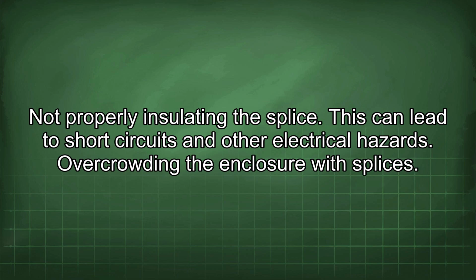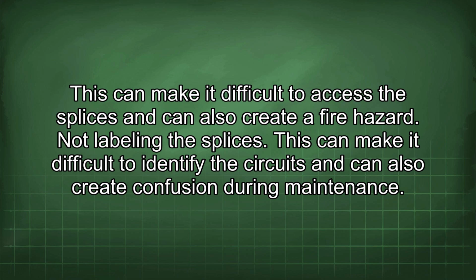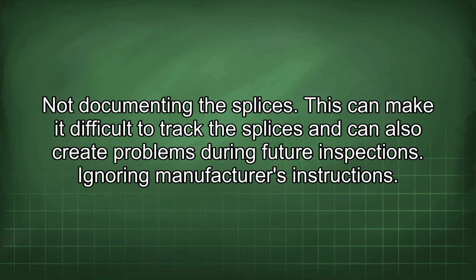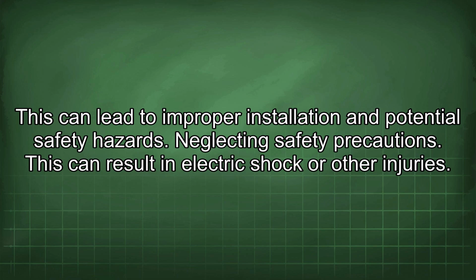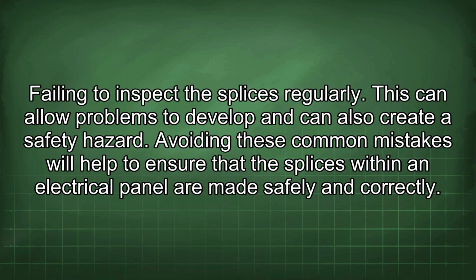Overcrowding the enclosure with splices. This can make it difficult to access the splices and can also create a fire hazard. Not labeling the splices. This can make it difficult to identify the circuits and can also create confusion during maintenance. Not documenting the splices. This can make it difficult to track the splices and can also create problems during future inspection. Ignoring manufacturer's instructions. This can lead to improper installation and potential safety hazards. Neglecting safety precautions. This can result in electric shock or other injuries. Failing to inspect the splices regularly. This can allow problems to develop and can also create a safety hazard. Avoiding these common mistakes will help to ensure that the splices within an electrical panel are made safely and correctly.